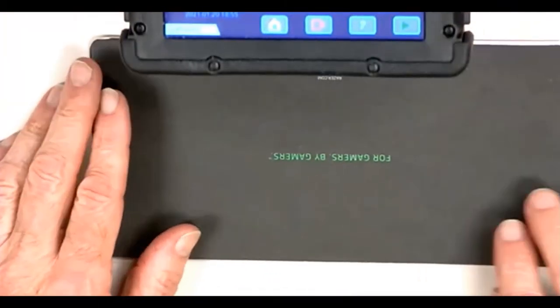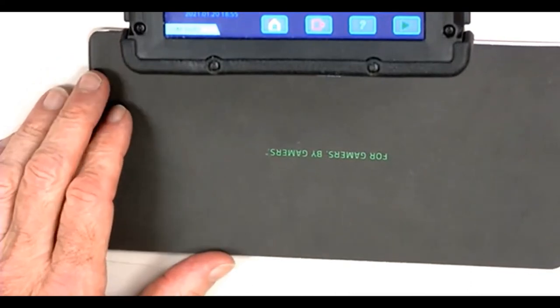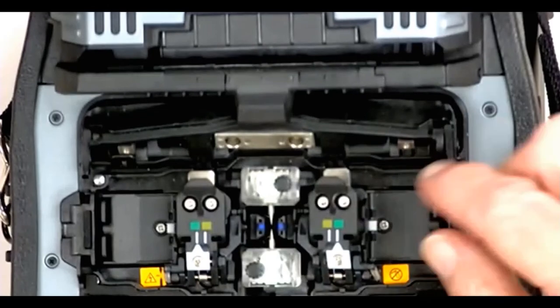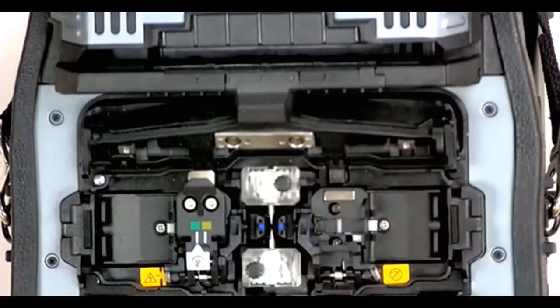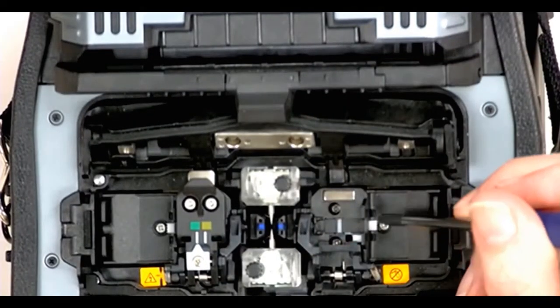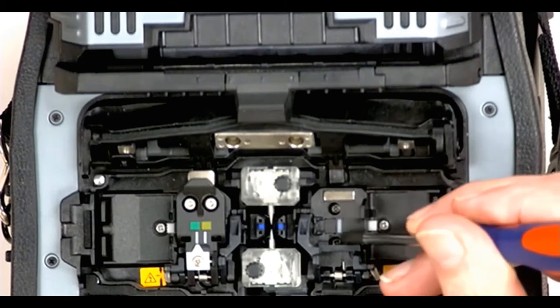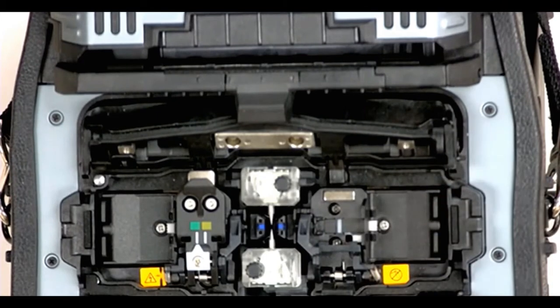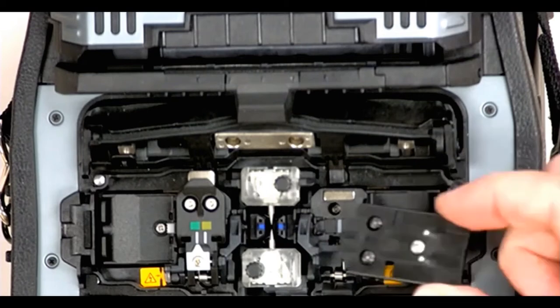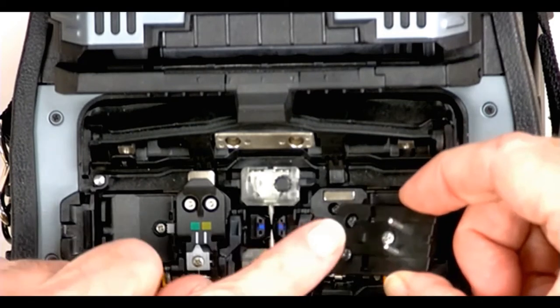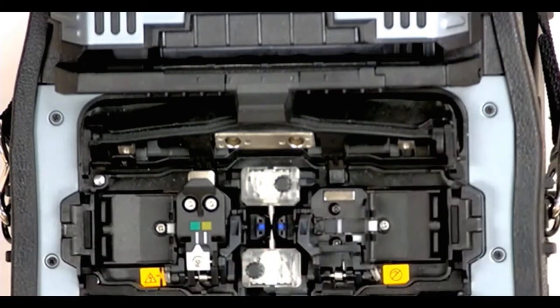As I mentioned before, we can remove this sheath clamp by pulling this screw, this screw, and this screw out. Then we can put this plate in here, and you can see it has these two guide pins. If we're going to splice Fuse Connect, we have to do that because we're going to be using a fiber holder system.